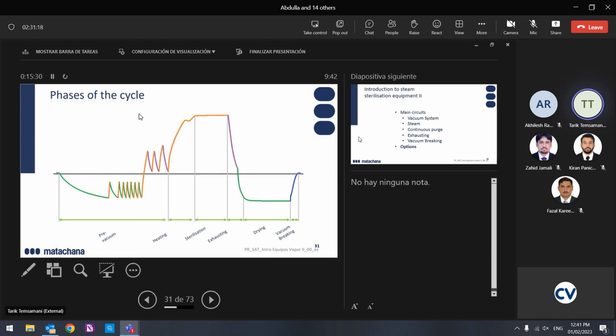Remember this profile. This is the cycle profile. This profile has to be here always. Why? The rhythm. It's clear, standard steam sterilization. Why? I come to the machine, I have a problem. Let's make the report. The problem is in this phase, the heating phase. What is the element in the heating phase? This element. So you can go directly to check what's happened. If you don't know how the machine is working, it's a problem. So we have the pre-vacuum, heating, sterilization, exhausting, drying, and vacuum breaking.